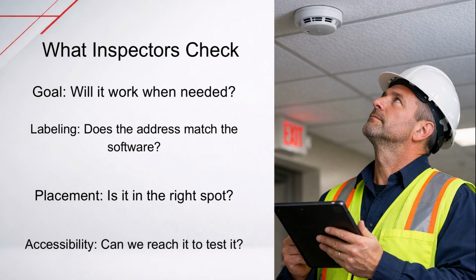When a fire inspector walks through your building, they are looking for a few specific things. First, is the location correct based on the floor plan? Second, is the device accessible for maintenance? Third, does the address label on the device match what the panel says? And finally, will it work when needed? They aren't trying to fail you. They are ensuring that if a fire starts, this plastic disc on the ceiling will actually do its job.